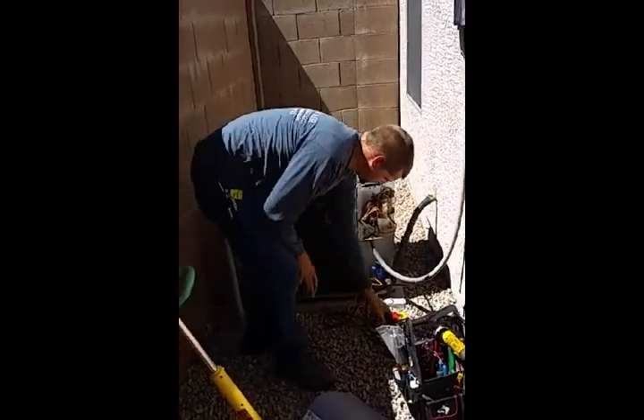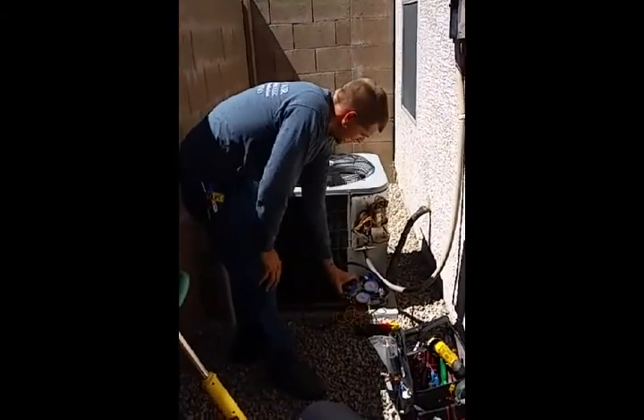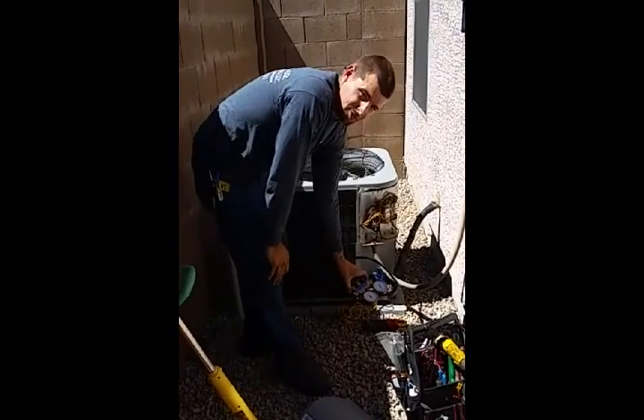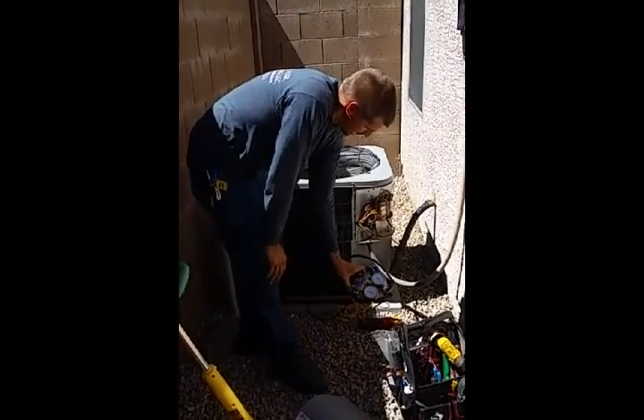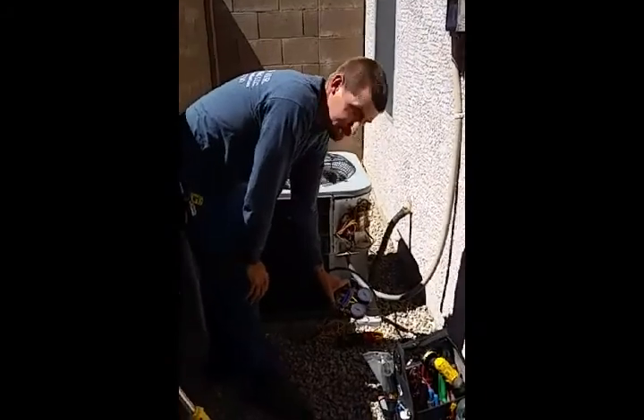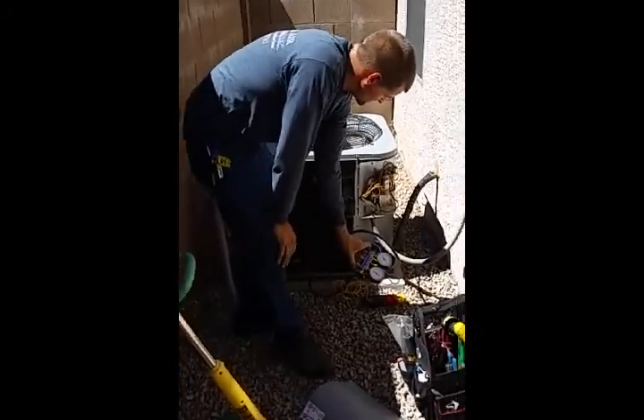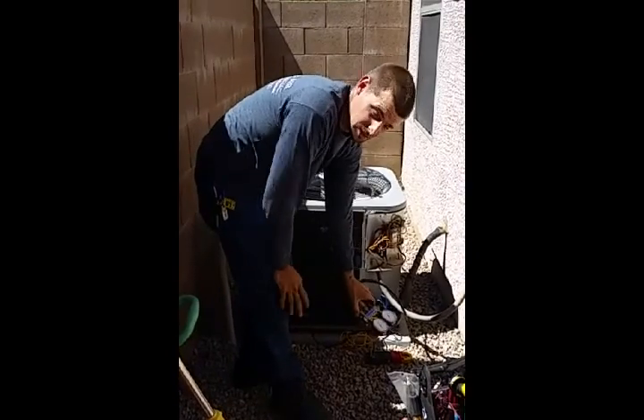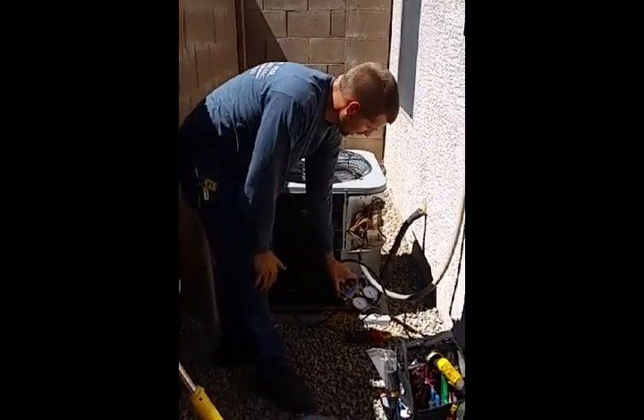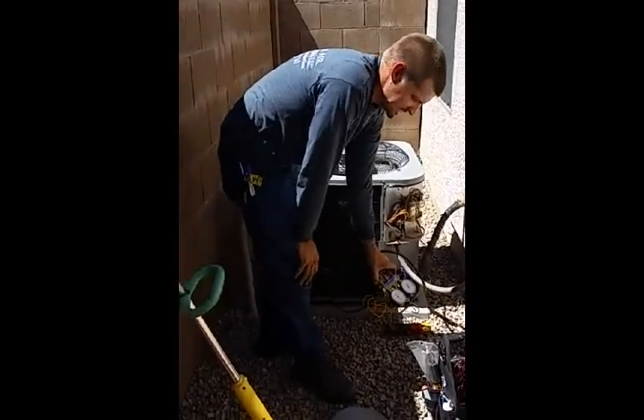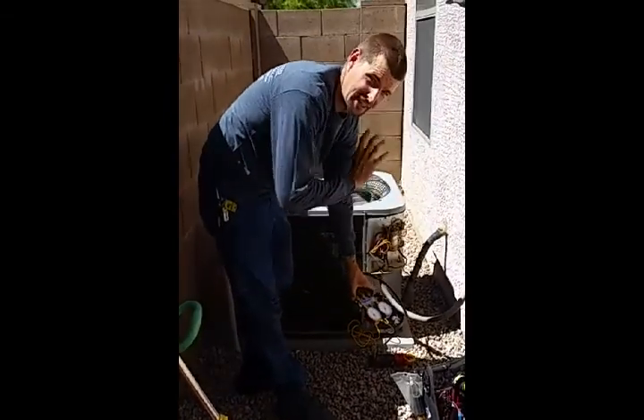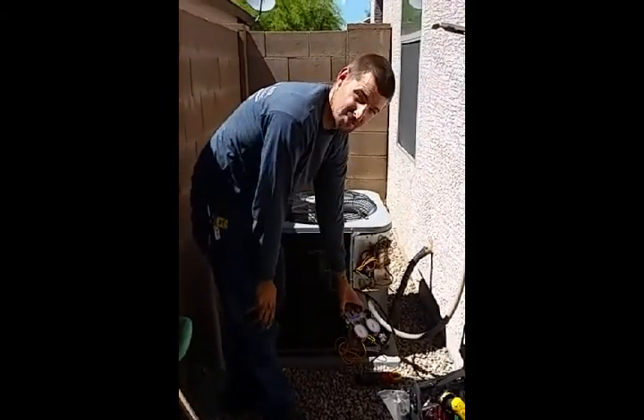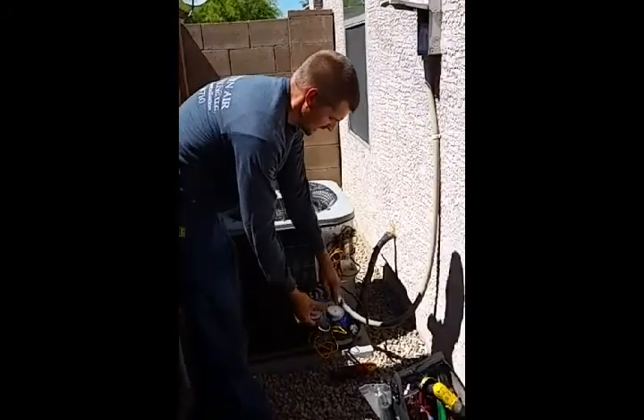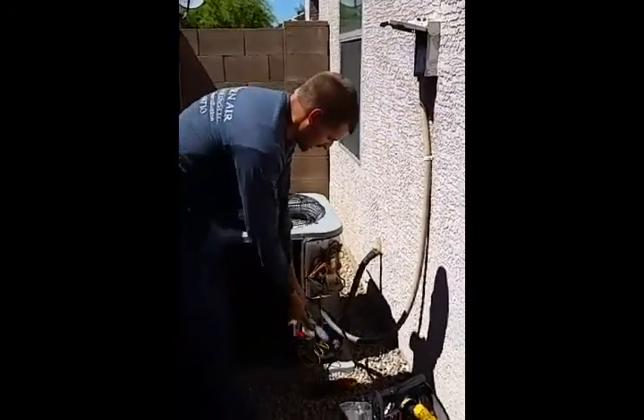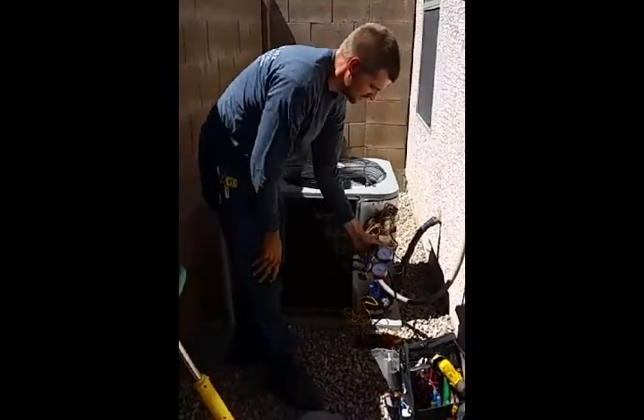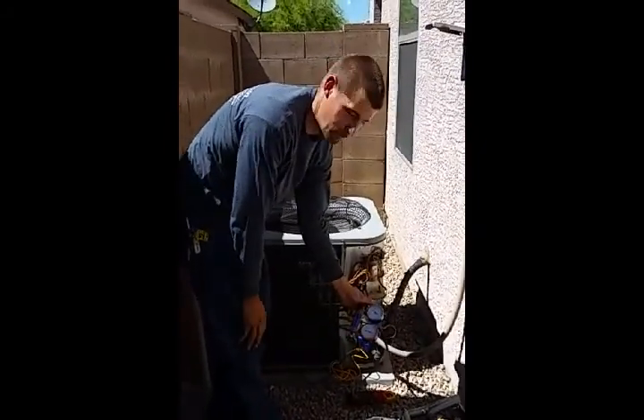And right now, we seem to be having right around 12 to 15 degrees. We're actually sitting at about 13.5 degrees of superheat. So the system is running really well right now. There are a couple obvious things on the indoor unit and the outdoor unit that I'm going to point out to the customer. We will see about getting it repaired. Freon wise though, looks to be sound. We don't have any issues with that. We won't have to add nothing.